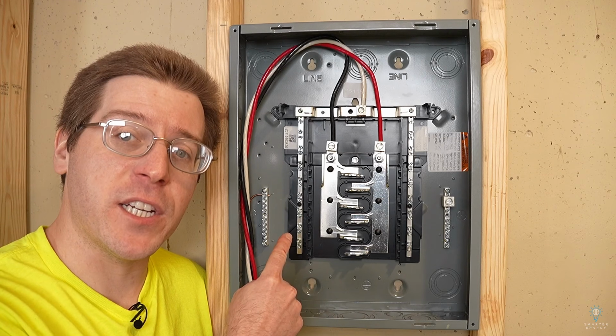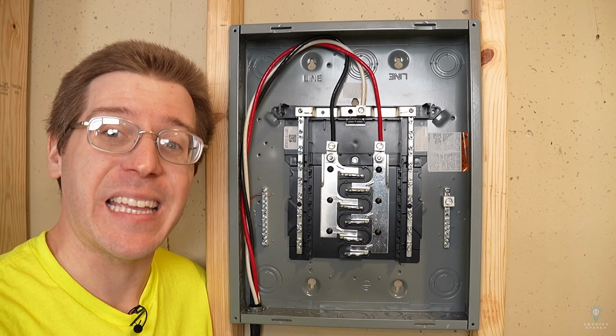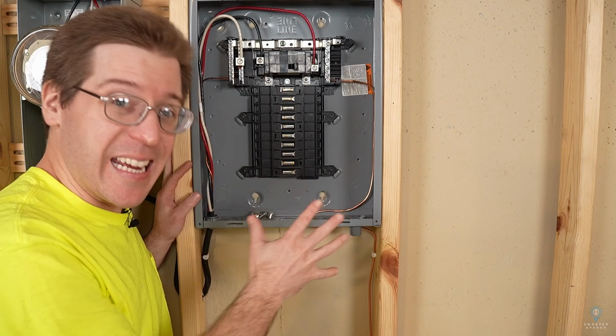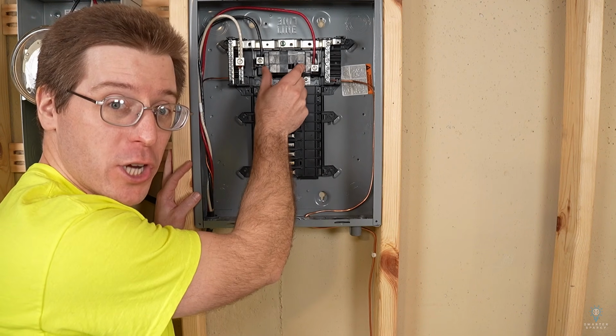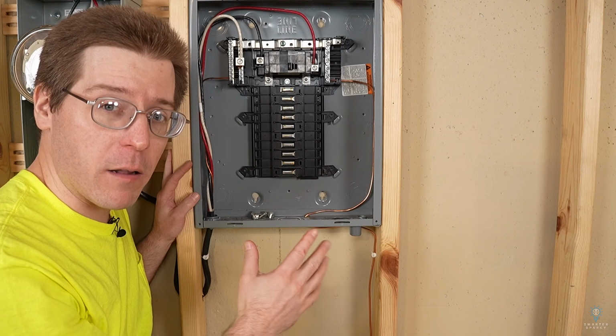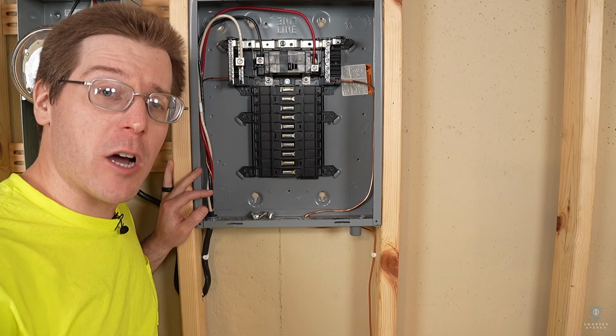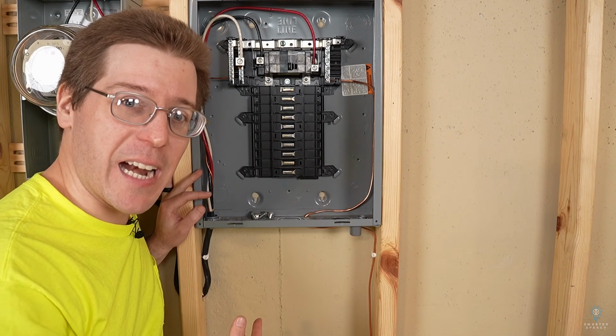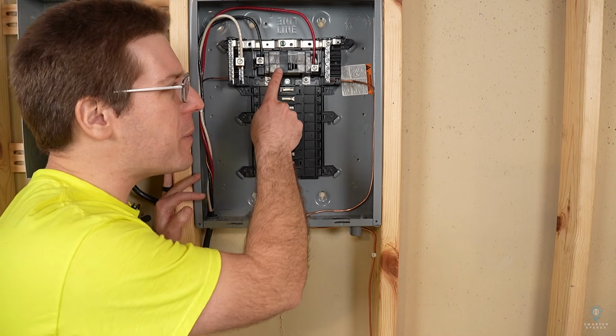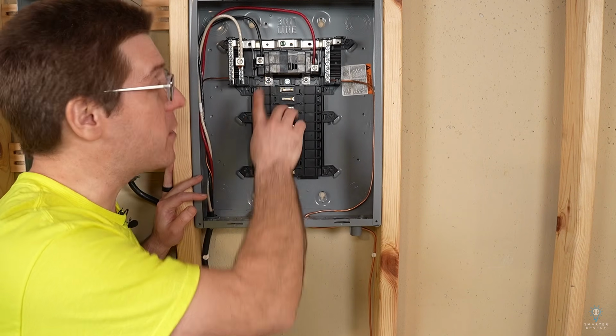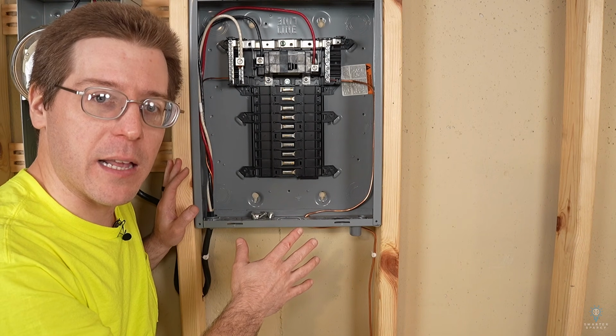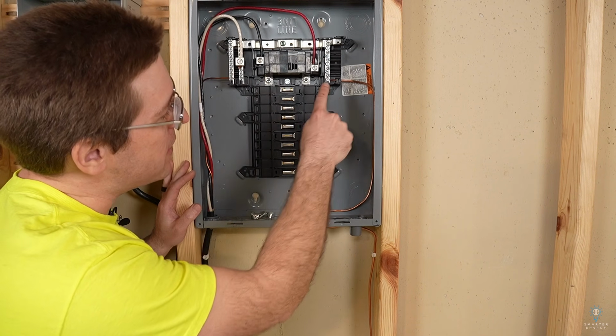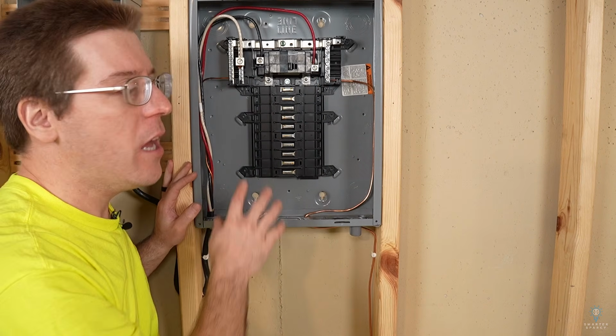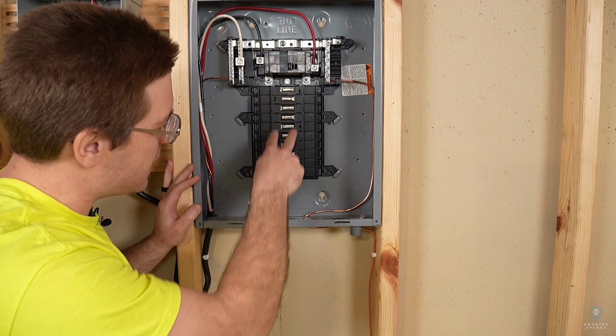The sub panel's finished for now. Let's head over to the main panel and get that wired. Anytime we're working in an electrical panel, we want to make sure we shut off the main power to that panel. After you're done watching this video, go check out my video explaining what's inside of a main electrical panel. Just because we shut off that main circuit breaker doesn't mean everything in this panel is dead. We would still have these energized lugs in here. The only thing this breaker shuts off is these bus bars.